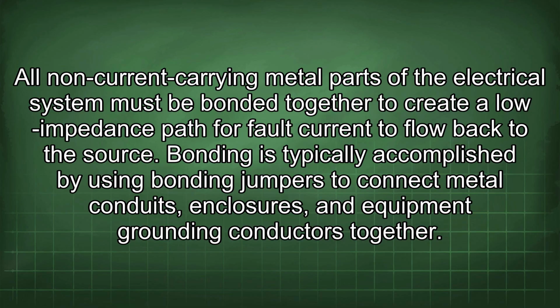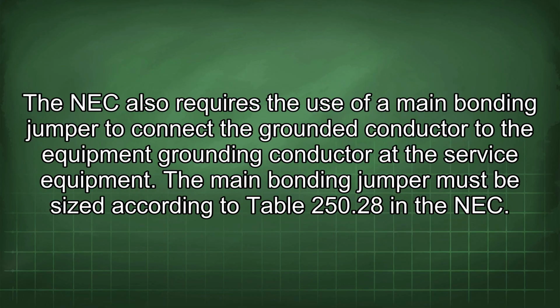All non-current carrying metal parts of the electrical system must be bonded together to create a low impedance path for fault current to flow back to the source. Bonding is typically accomplished by using bonding jumpers to connect metal conduits, enclosures, and equipment grounding conductors together. The NEC also requires the use of a main bonding jumper to connect the grounded conductor to the equipment grounding conductor of the service equipment.